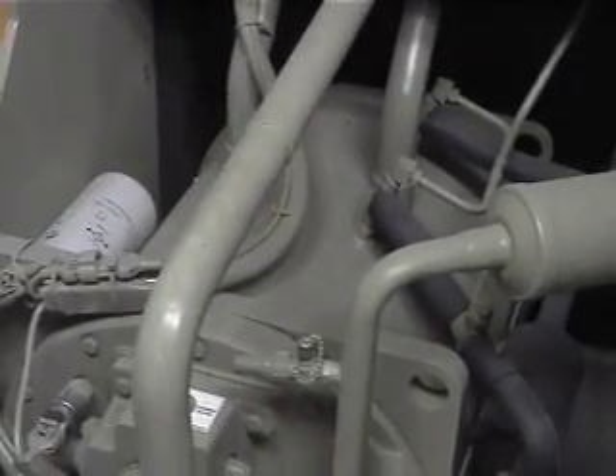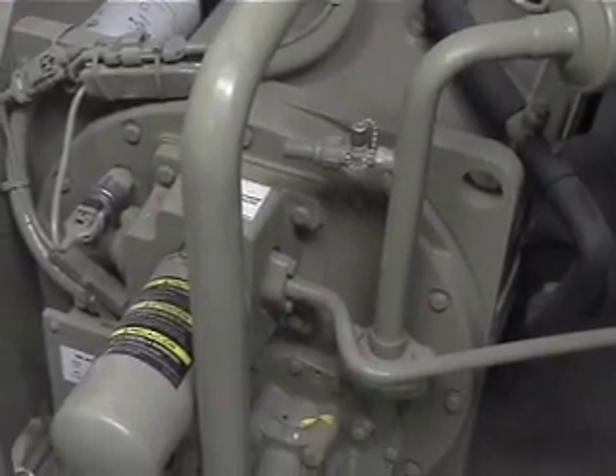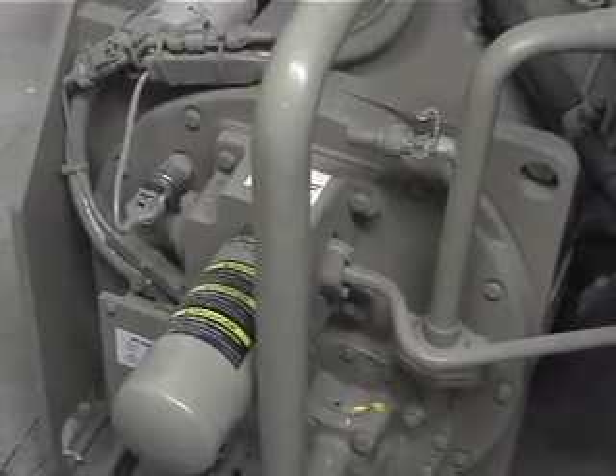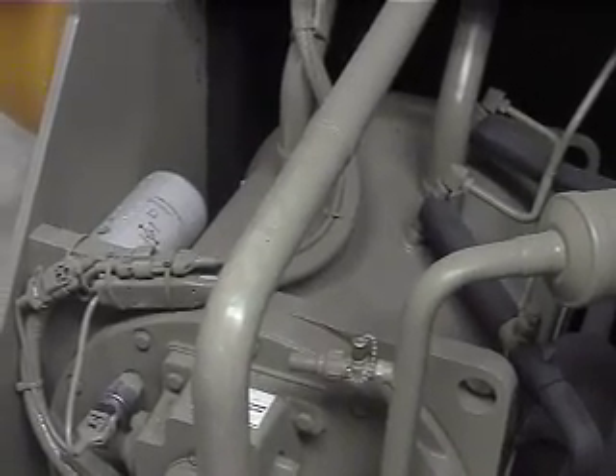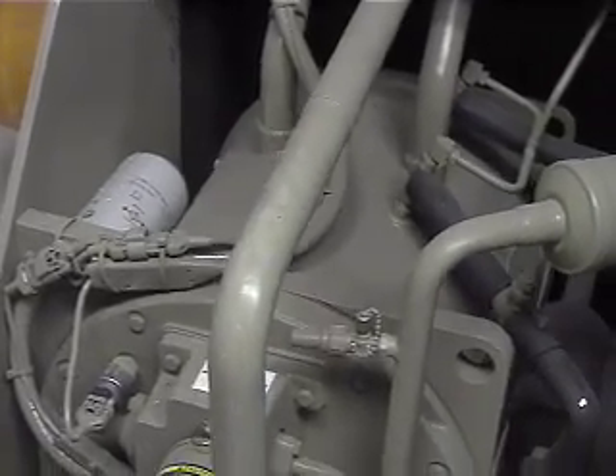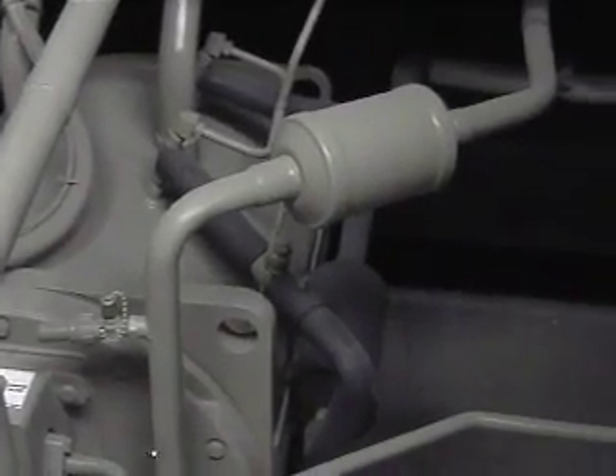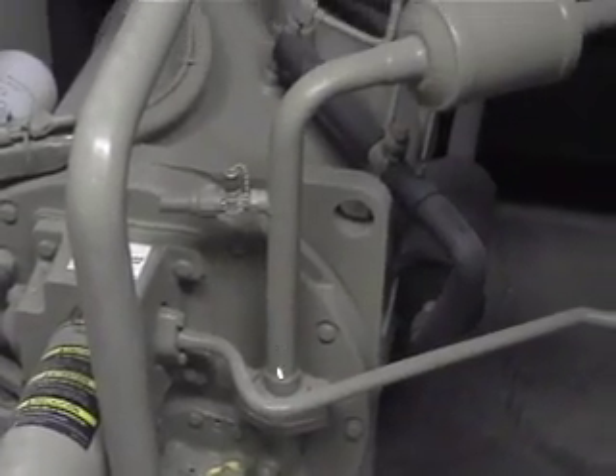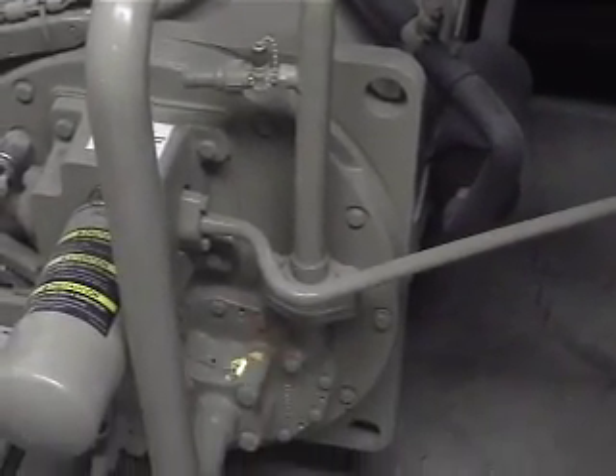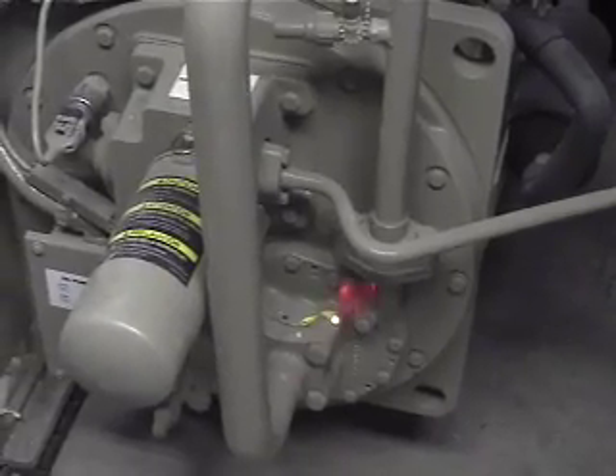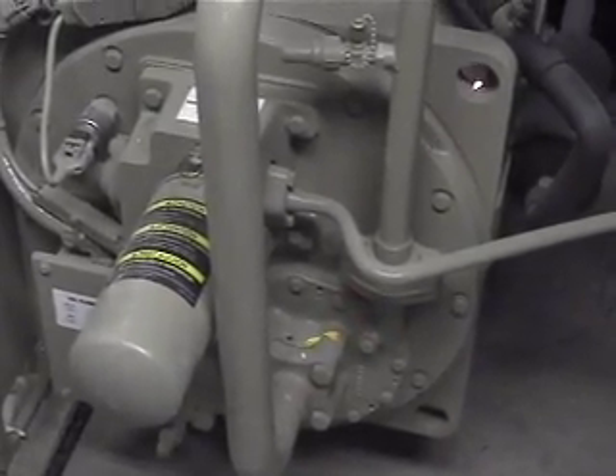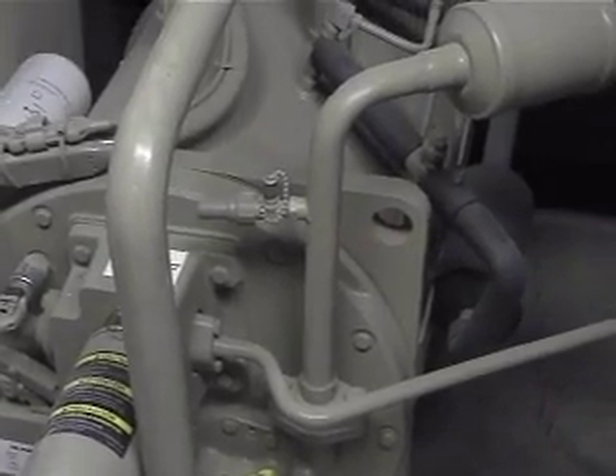Right here is what we were talking about as far as the oil sump. This is one of the things that's different than on your other two chillers. They put it down here, and we've got your refrigerant line that comes in right here. That's your refrigerant pump right there on the outside. On the back side of that, you've got your oil pump, which is sending your oil out to that line up there on the compressor.